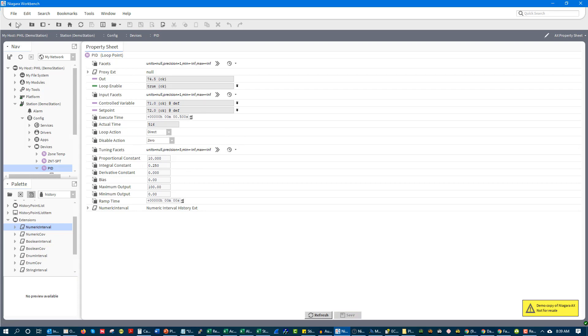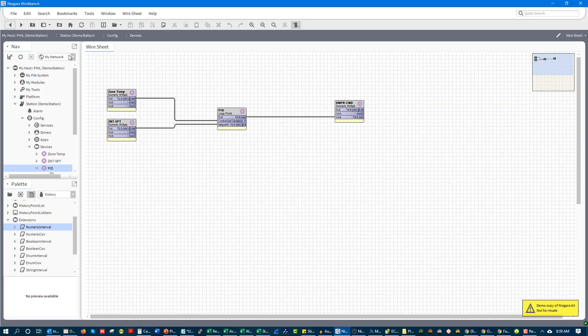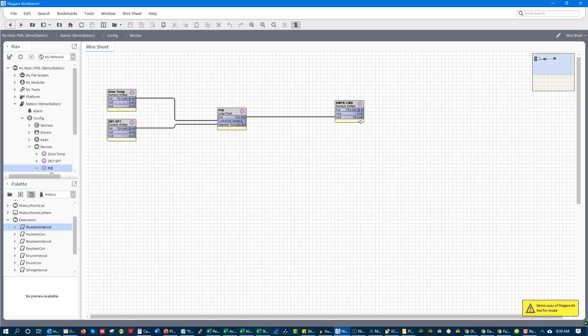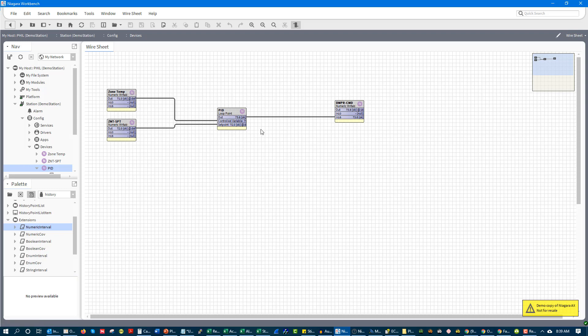Now there's this I thing, right? So in theory, you could just have proportional response and you would get some controllability from it. The problem is, is that it's going to proportionally respond to the error, and you can get situations where it's just not very responsive. As the error increases, it will eventually drive the PID loop to 100% when it gets to the top of that sensor span.